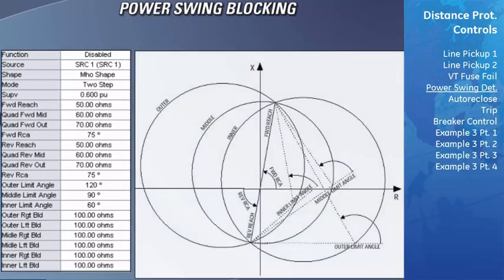The next group of settings is used to define the shape and size of the power swing blocking zone. If the mho shape was selected in the shape field, the following settings need to be set. The power swing forward reach setting specifies the overall size of the forward reach of the blocking zone. This setting should be set higher than the sum of the transmission line and remote source positive sequence impedances. The power swing forward reach characteristic angle specifies the angle of the forward reach impedance. The angle is measured from the positive x-axis as shown here. The power swing reverse reach setting specifies the overall size of the reverse reach of the blocking zone. For a simple system consisting of a line and 2 equivalent sources, this reach will be higher than the positive sequence impedance of the local source.